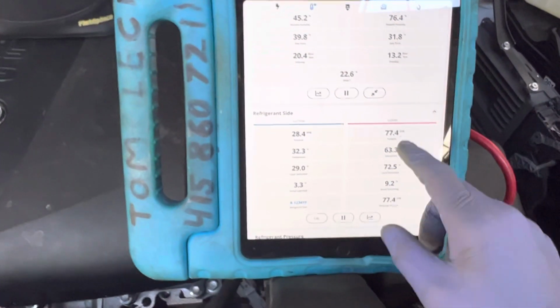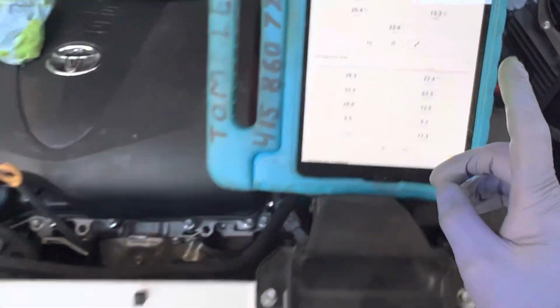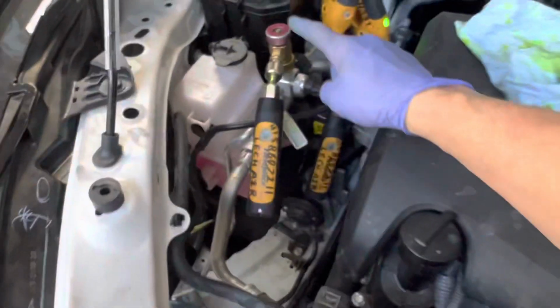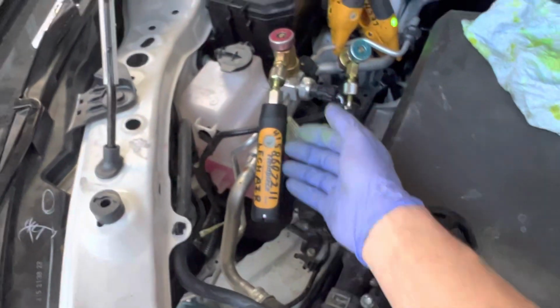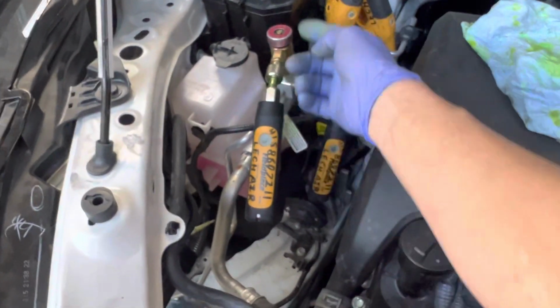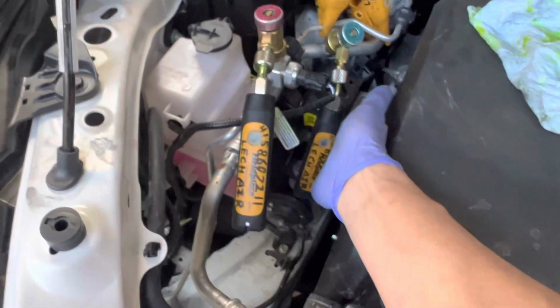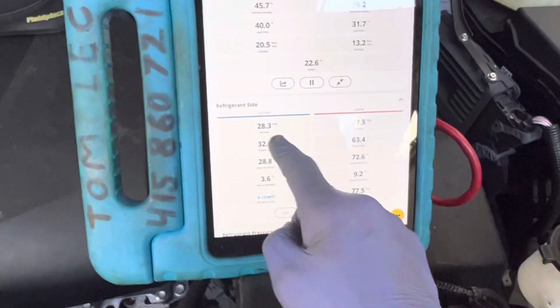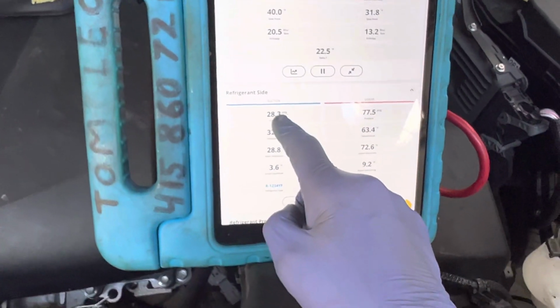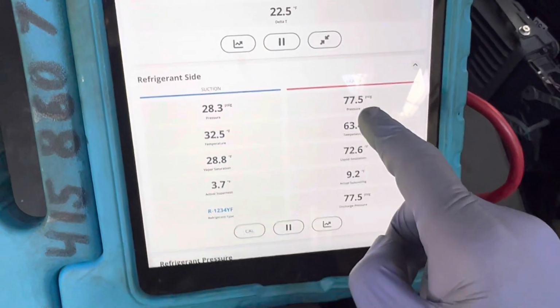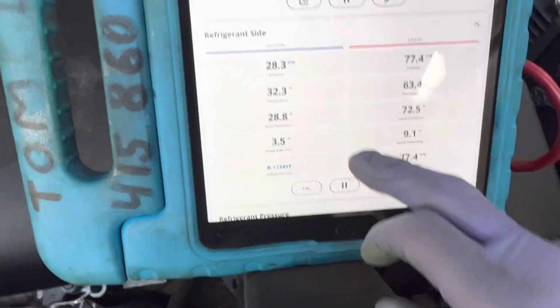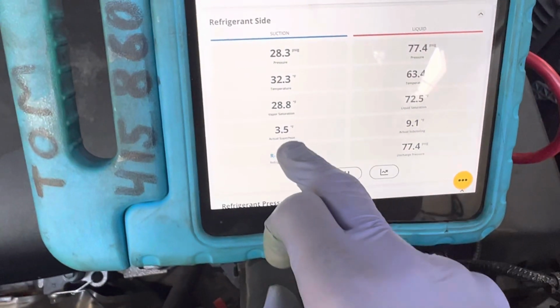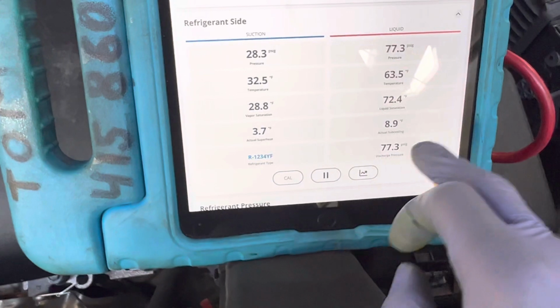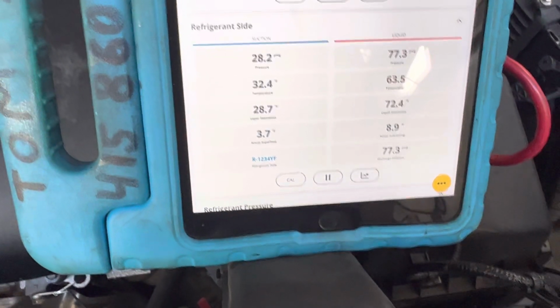If we come back to pressures, we're at 77 PSI on the high side. The high side pressure is being read by a Bluetooth transducer right here from Fieldpiece going to the high side. Low side transducer, live data streaming right now. We're at 28 PSI on the low side, 77 PSI on the high side. We have 3.5 degrees superheat, 8.9 degrees subcooling.